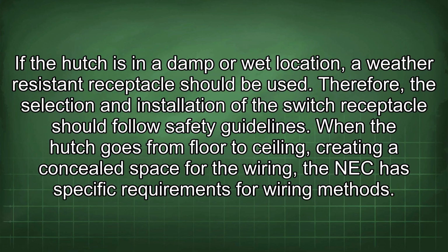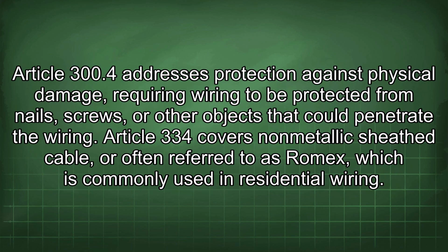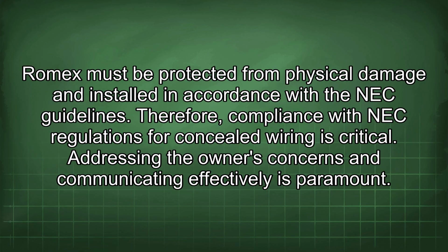When the hutch goes from floor to ceiling, creating a concealed space for the wiring, the NEC has specific requirements for wiring methods. Section 300.4 addresses protection against physical damage, requiring wiring to be protected from nails, screws, or other objects that could penetrate the wiring. Article 334 covers non-metallic sheathed cable, often referred to as Romex, which is commonly used in residential wiring. Romex must be protected from physical damage and installed in accordance with the NEC guidelines. Therefore, compliance with NEC regulations for concealed wiring is critical.